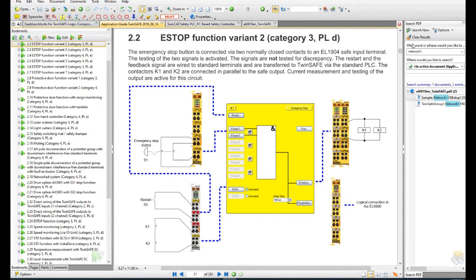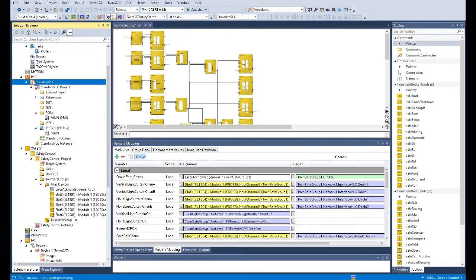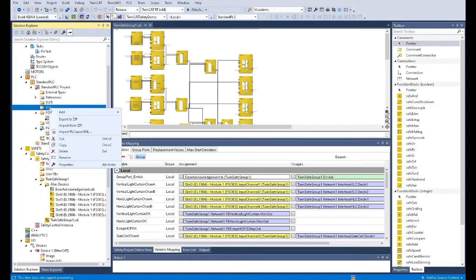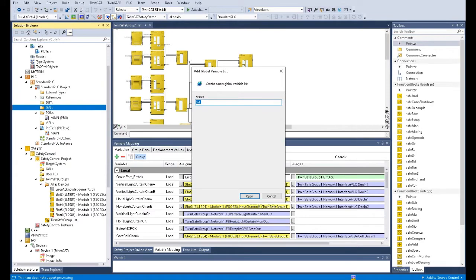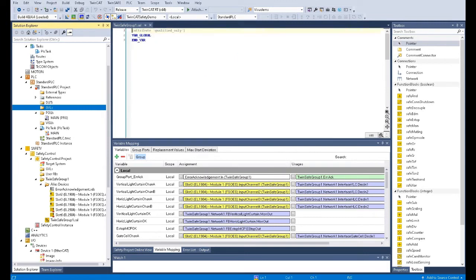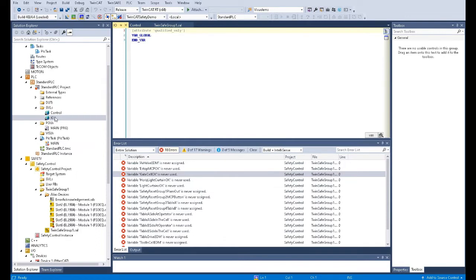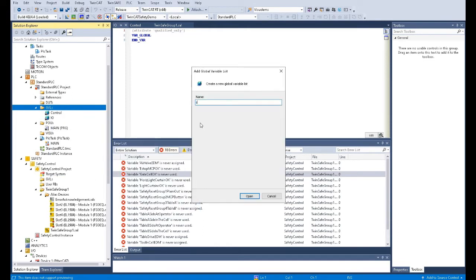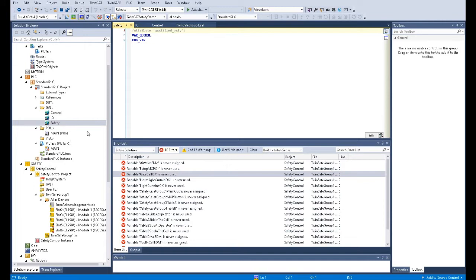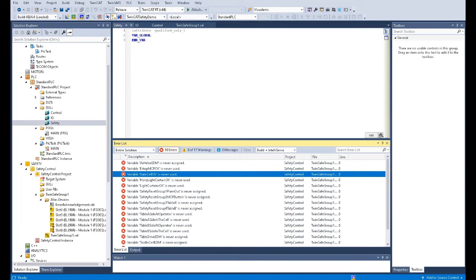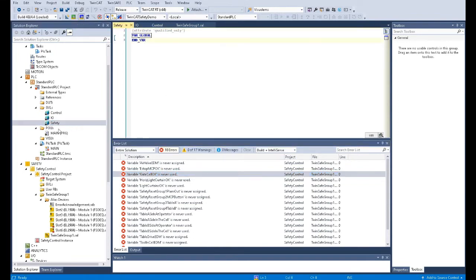The restart signal also comes from the standard PLC. Firstly we need to create the tags from the standard PLC area. To create the tags, we go to the global variable lists (GVLs) and add a global variable list. In an actual project, I prefer to create three groups: the first one is 'cell' or 'control,' the second is 'IO' where all physical input and output channels are placed, and the third is 'safety' — all signals used to exchange data between the standard PLC and the safety PLC will be created under this folder.